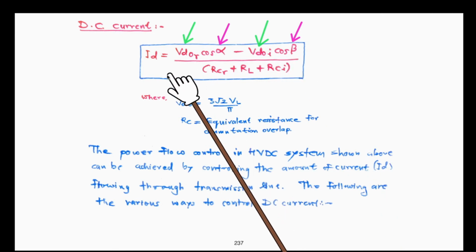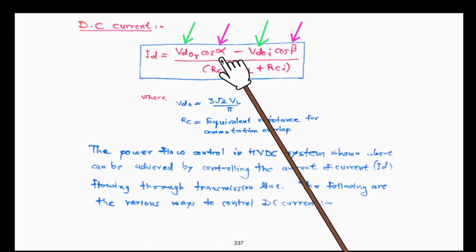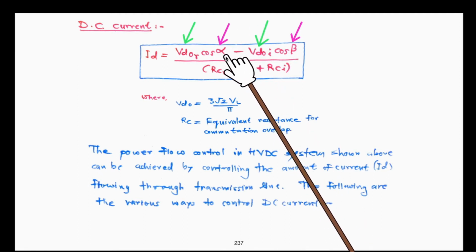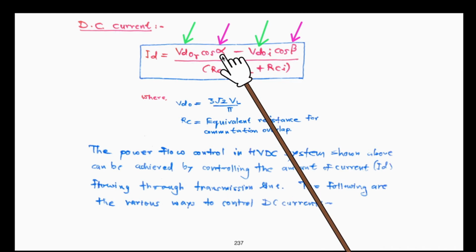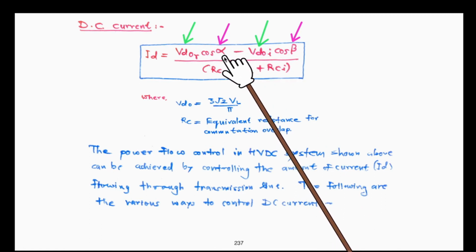And they can adjust the DC current very rapidly, and not only do they provide tremendous flexibility of operating one end converter both as a rectifier and also as an inverter. So this means that not only can it adjust the firing angle, it can even make power flow in the reverse direction by adjusting the firing angle control.